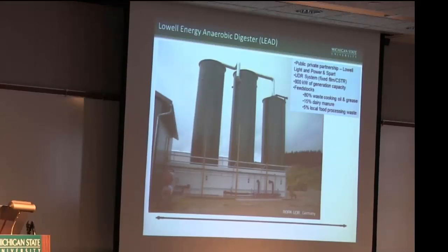So you have to be very dilute, and you generally want your organic waste to be dissolved or very, very fine particles. But these towers are packed with media, and they create a biofilm in there. That biofilm is what's used to treat and convert that organic waste into biogas. So this system is UDR, upflow, downflow, and then reflow, which sends some back. There's a tank that's not shown, and there is a complete mixed digester that sits on the back end.